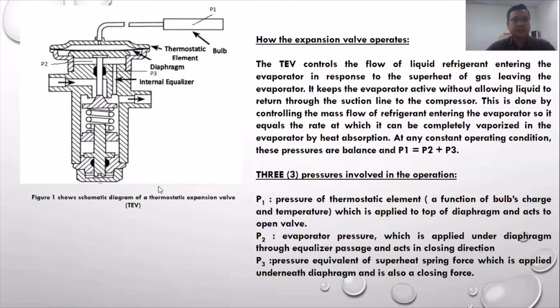This one actually is for the expansion valve, operating the same as the external expansion valve. So if you have high pressure, this is one of the sensors, the high pressure will push the diaphragm to open the flow.